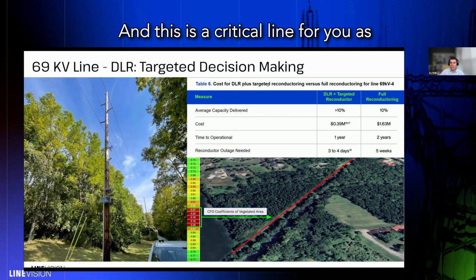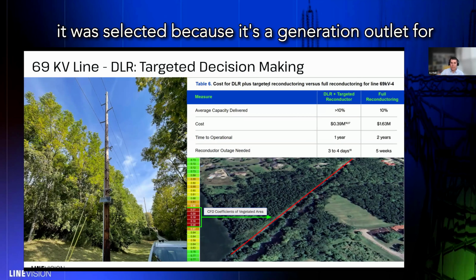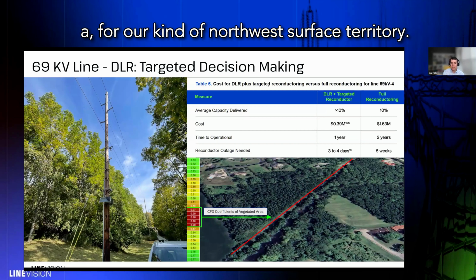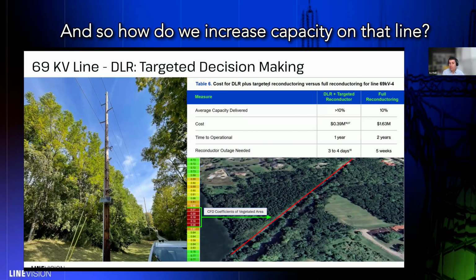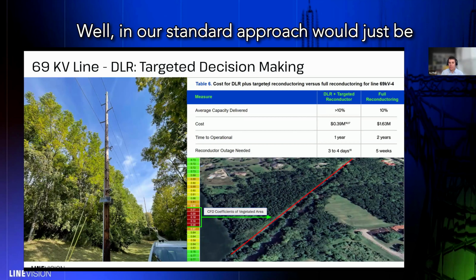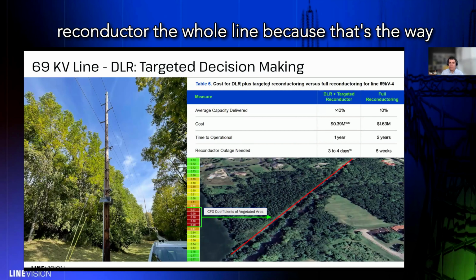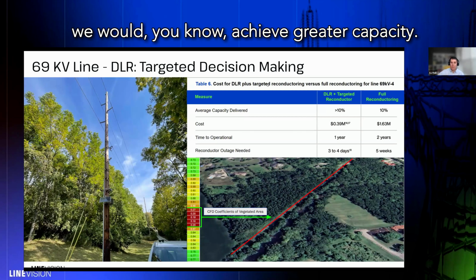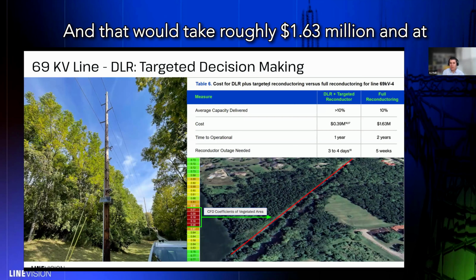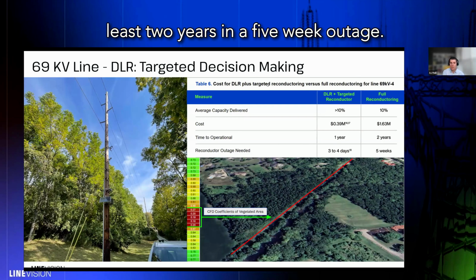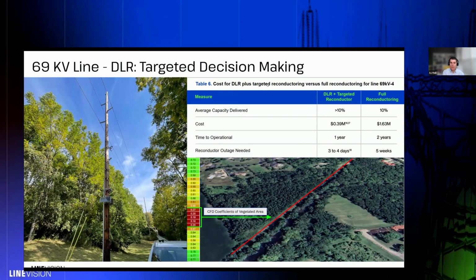This is a critical line for AES. It was selected because it's a generation outlet for our northwest service territory. So how do we increase capacity on that line? Well, a standard approach would just be to reconductor the whole line, and that would take roughly $1.63 million and at least 2 years with a 5-week outage.